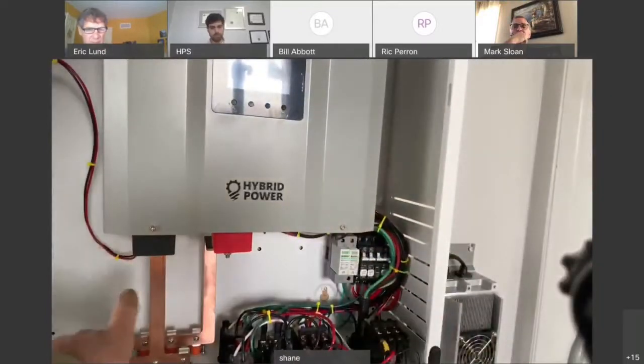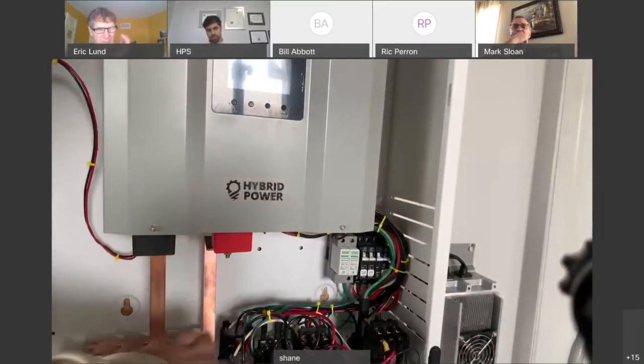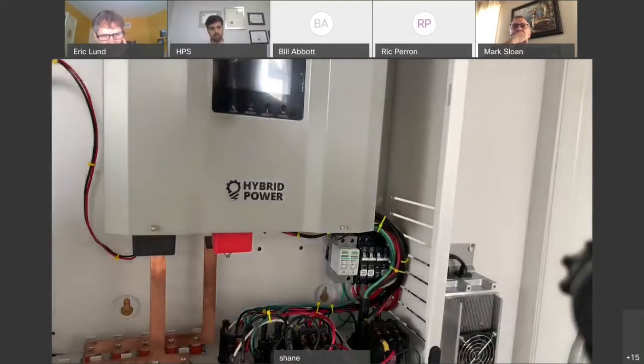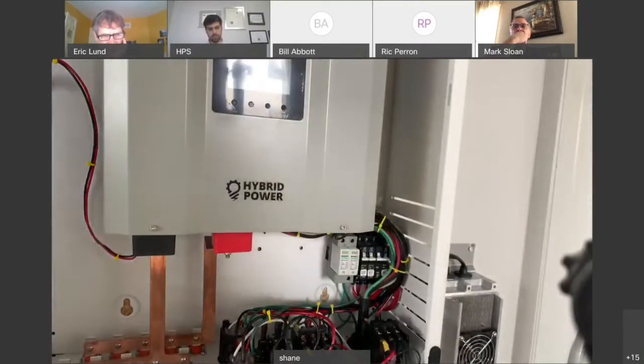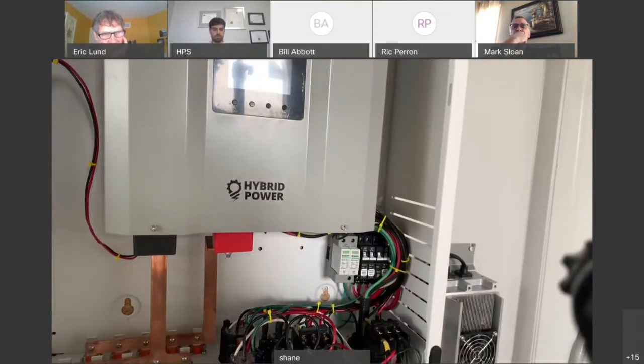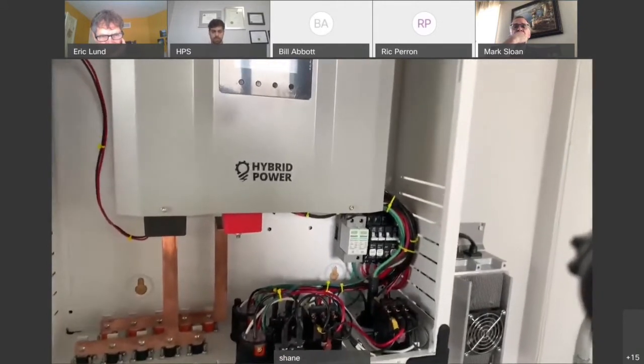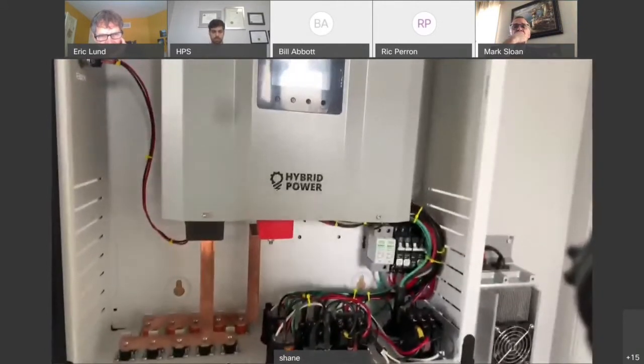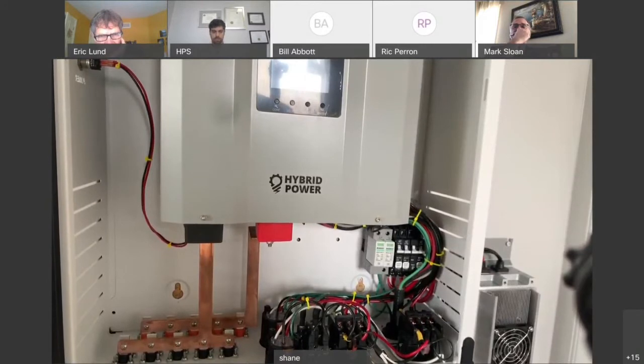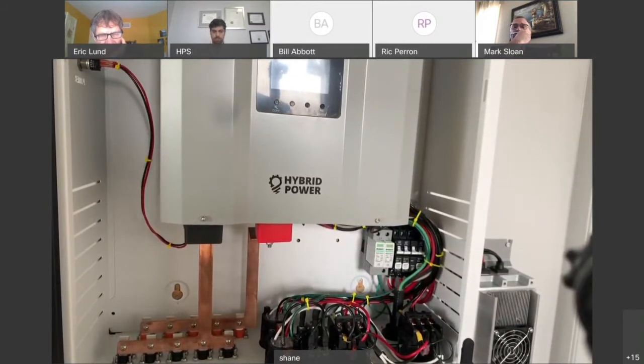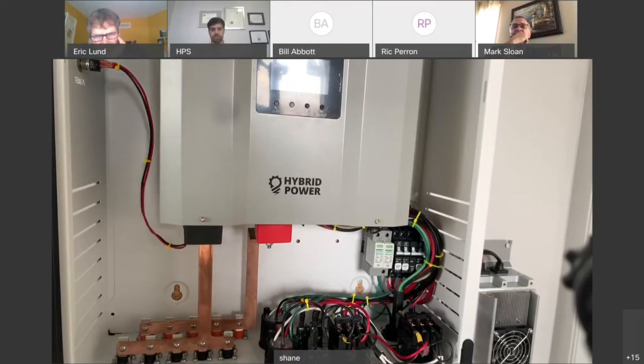You have your negative bus, your positive bus coupled into your battery. So everything goes through those bus bars on the current flow towards the batteries and out from the batteries. So they're rated properly to handle up to 60 kilowatt, I believe. Obviously, we're not going to be able to pull that because we only have 6 kilowatts to pull. So that's what, 6 kilowatt at 48 volts. That's how many amps? Not that many. So we have only 125 amps going through that bus bar at peak.